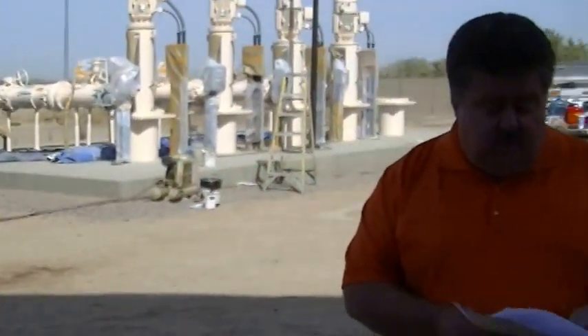Okay, the first thing we want to address in this training is safety. There are AC and DC circuits in this equipment that are over 48 volts. Over 48 volts is not touch safe, it will kill you. Also, some of the DC circuits in the drives are near 700 volts, and they have capacitors in there so they can stay charged up to 15 minutes. If there's nothing to discharge that capacitor, it could stay at 700 volts for a very long time, so keep your hands out of the equipment unless you're properly trained and qualified.